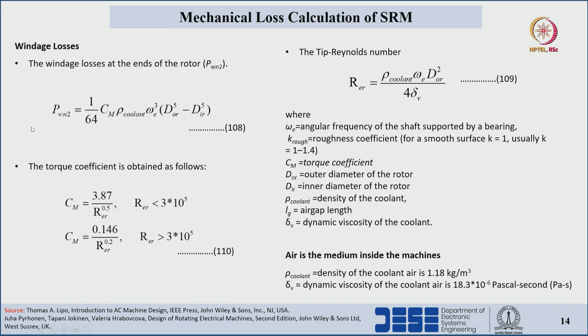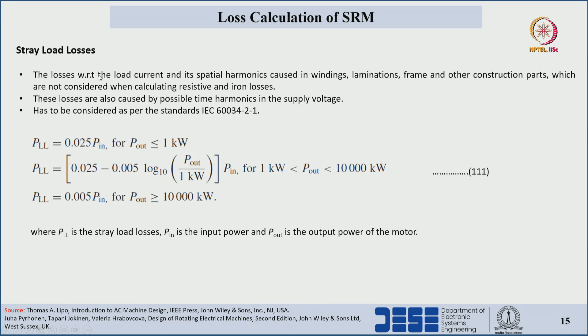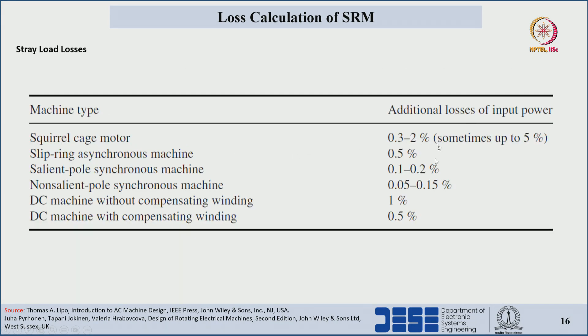Based on the Reynolds number, the windage losses at the end of the rotor can be calculated. Stray load losses are losses from load current and its spatial harmonics in the windings, laminations, frame, etc. — the remaining losses not covered by windage, copper, or core losses. As a percentage: for induction motors approximately 0.3 to 2%, for salient pole synchronous machines 0.12%, and for switched reluctance machines the range is 0.1 to 0.2%.